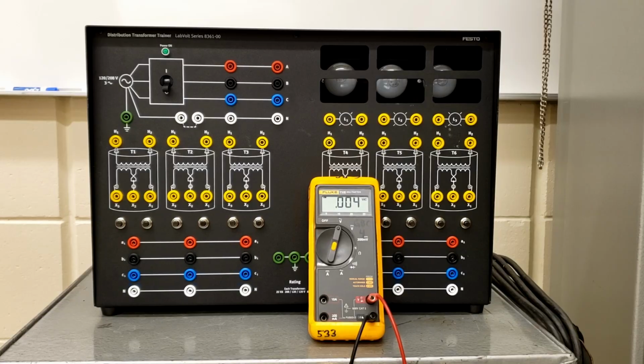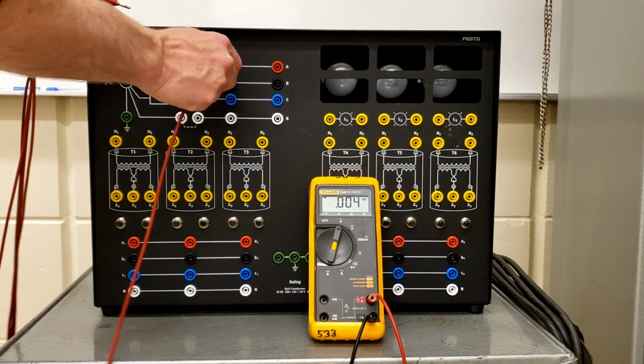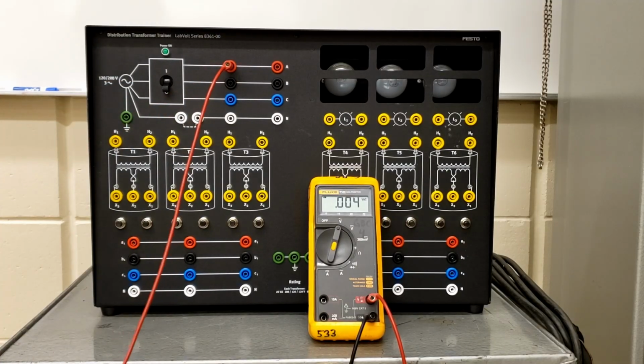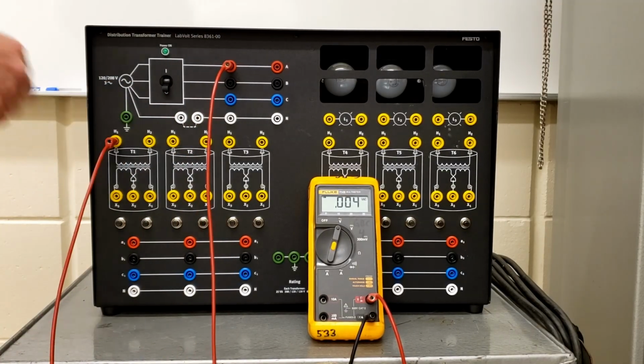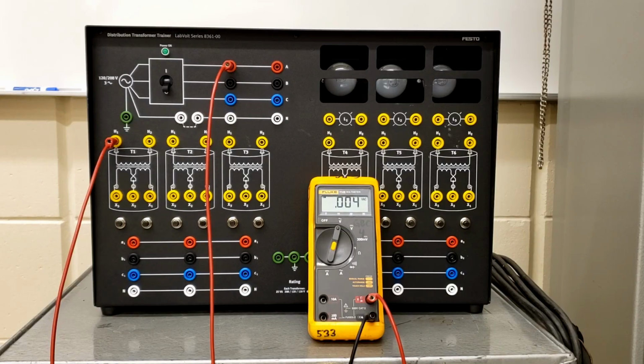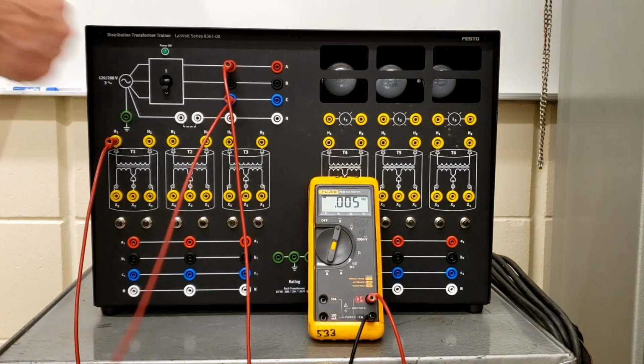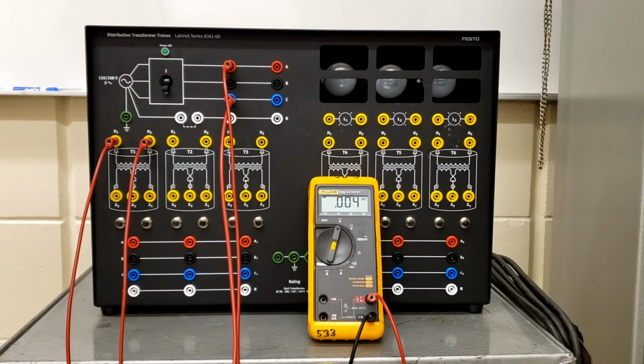Okay guys, last one, page 21 of the student manual, page 25 of the instructor manual. We're doing delta Y 30-degree phase shift now. So don't go on cruise control, watch the wiring there. Looks like the first transformer, because usually we're doing A to B, B to C, C back to A, right? But taking a look on page 21, we have the wiring for transformer number 1. A is definitely going to H1. But if you take a look at H2 of transformer number 1, it's going to C. Okay, so don't be on cruise control, watch the diagram there.